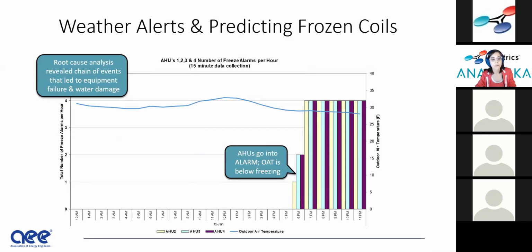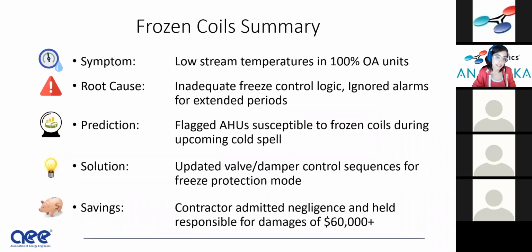I'm going to go quickly through this example. This is a weather alert. We just see some alarms here flagging that are going into alarm mode when the OAT drops below freezing. Really, I just wanted to use this as an example of when we can flag air handlers that are susceptible to frozen coils for an upcoming cold spell or hot spell, for example. When we're towards ASHRAE design conditions for weather, that's when we're going to monitor this equipment and predict units that will have problems, again, based off of past operation and things like that.